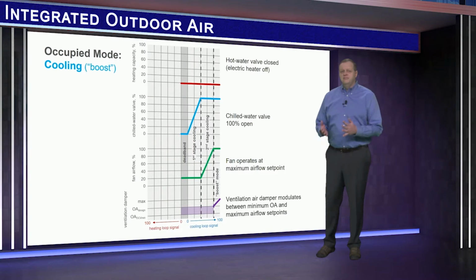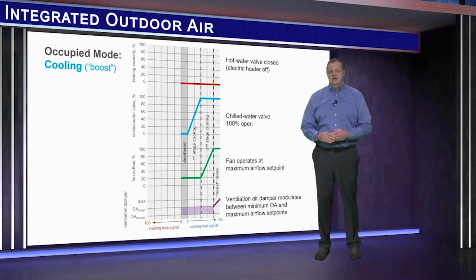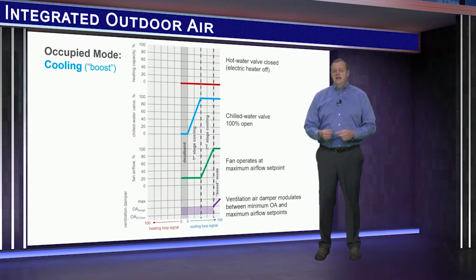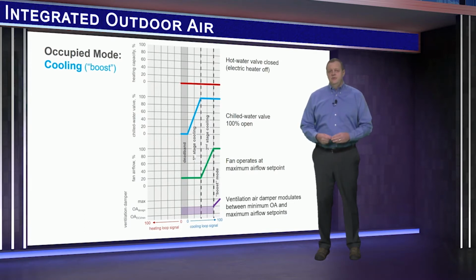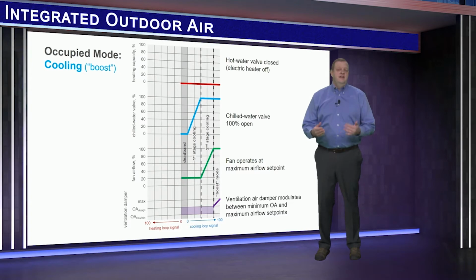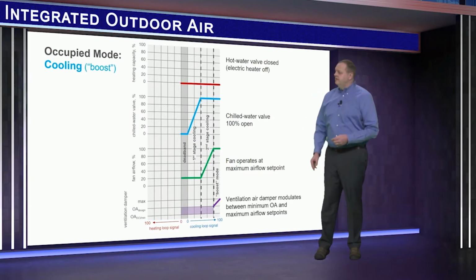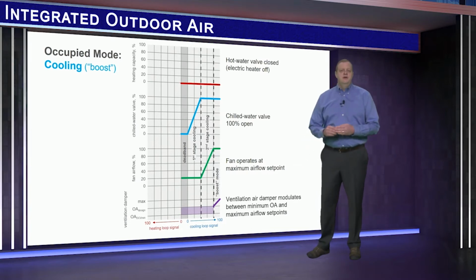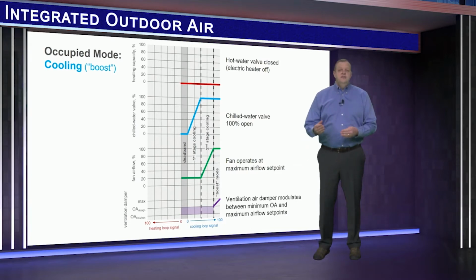Now, note that this boost mode is not intended to be typical operation. The terminal unit should be selected to offset the design space-sensible cooling load with the fan at full speed and the chilled water valve 100% open. This boost mode is meant for unintended situations that might not have been considered when sizing, like 30 people cramming into a conference room that was designed for 20. This maximum damper airflow set point is an adjustable setting, so you can decide how much or how little boost you want to design in.